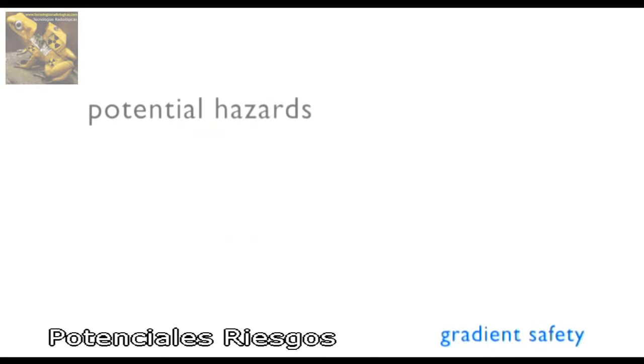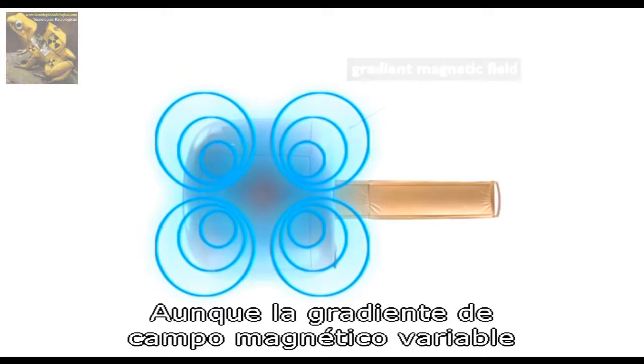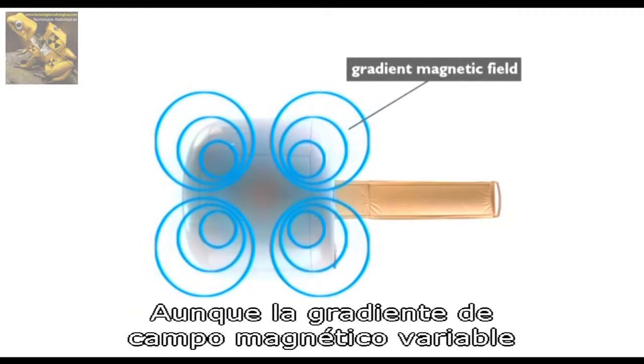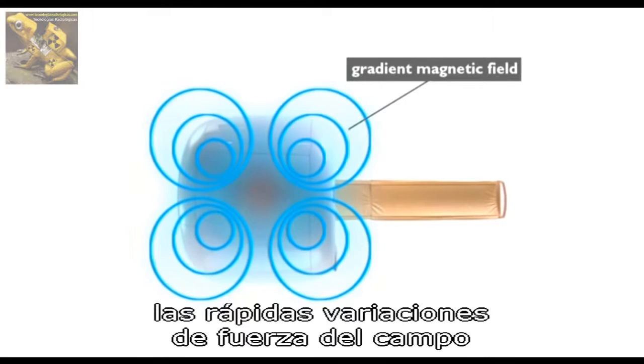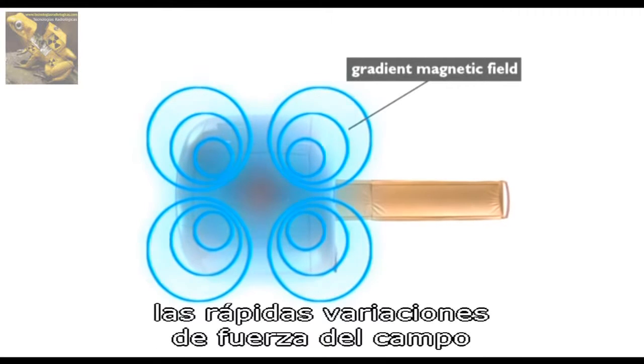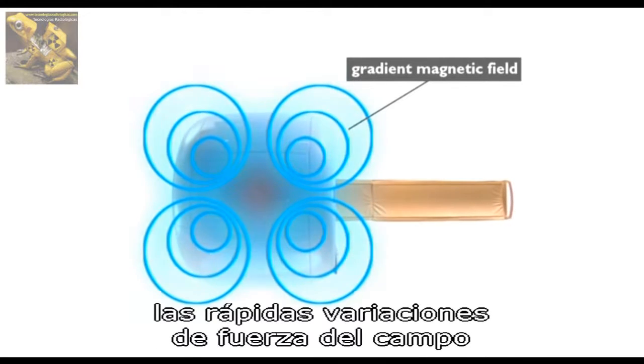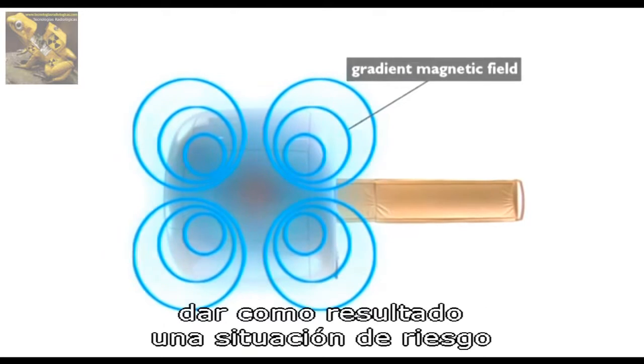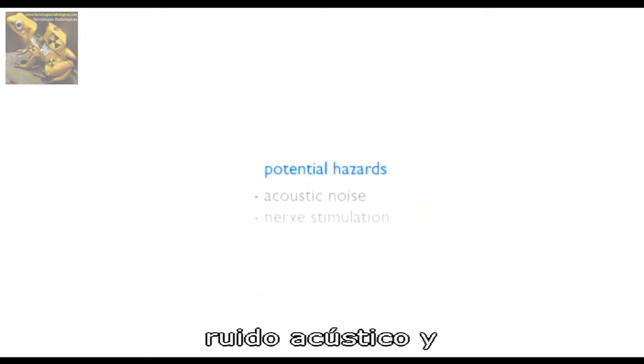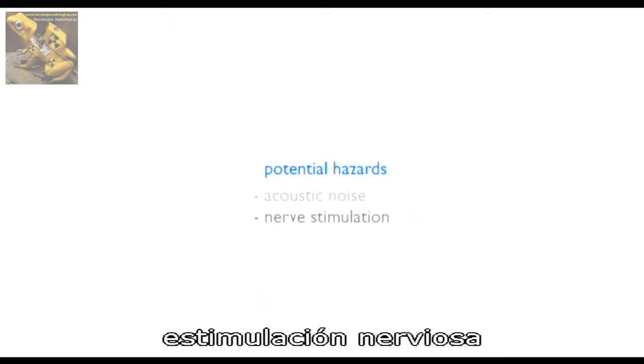Although the switched gradient magnetic field is much weaker than the static magnetic field, the rapid changes in gradient field strength present two different effects that may result in a hazardous situation. These are acoustic noise and nerve stimulation.